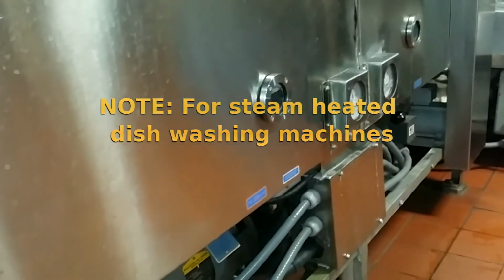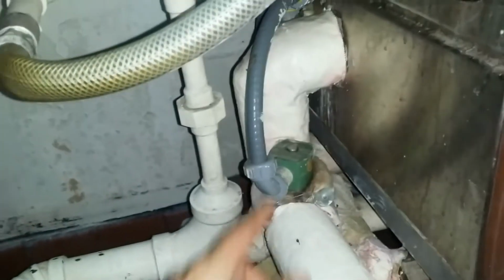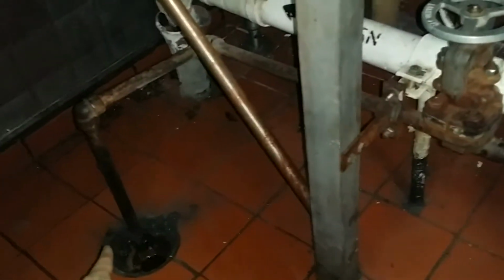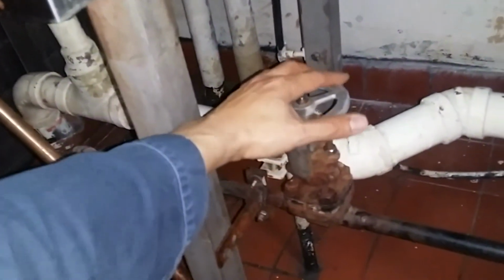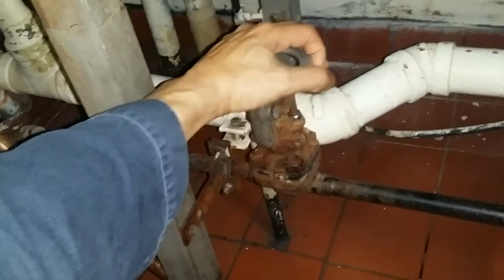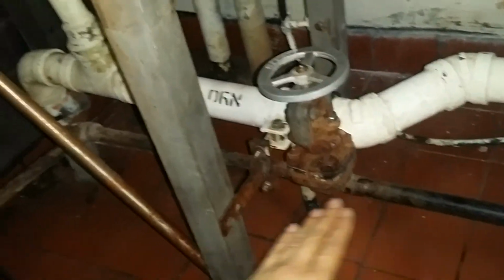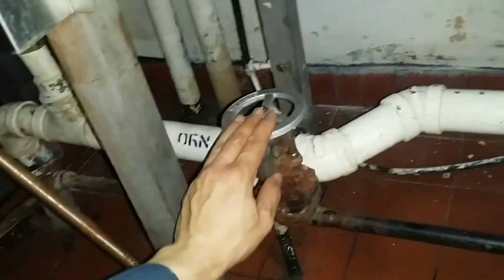Service calls are made because this steam Scullery doesn't get up to temperature, and often the problem is not that our solenoids go bad. It's that people decide, because it gets too hot over here with the steam, to close the steam drain valve, and this valve should always be open to allow steam to go out. If the steam cannot go anywhere, it's not going to circulate and it's not going to keep the temperature.